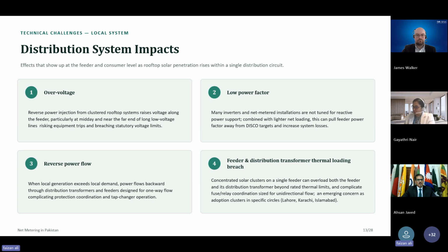One is the overvoltage. There is a phenomenon that whenever you supply power back to the grid, or in any case oversupply power, you will face overvoltages in the network. So with reverse power flows, with people installing clustered rooftop solar systems in small, narrow streets, you will see that during the shoulder months the skies are clear. It is an ideal situation, and the load of the residential or commercial systems is relatively less. So you will see a lot of feedback, and due to that feedback the overall network will undergo overvoltage.